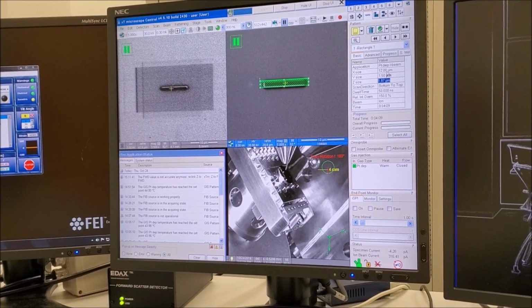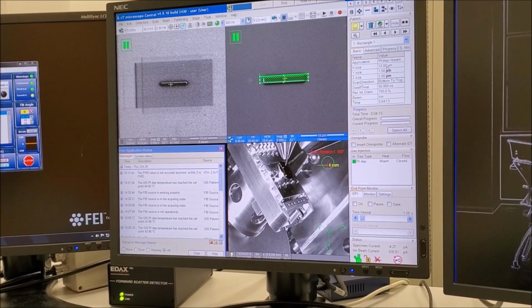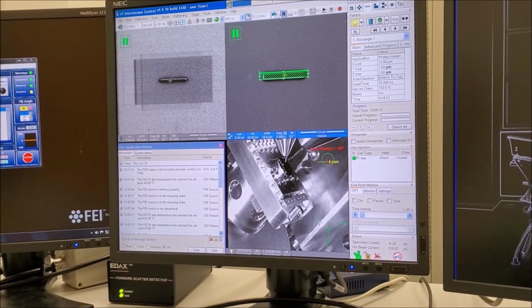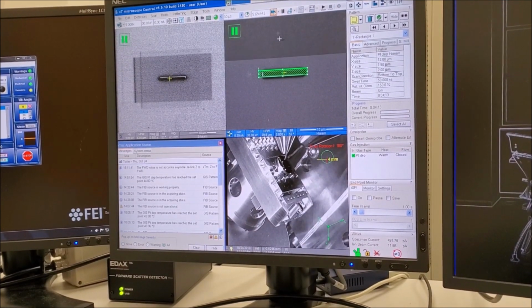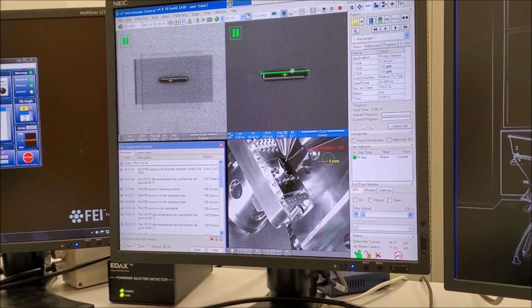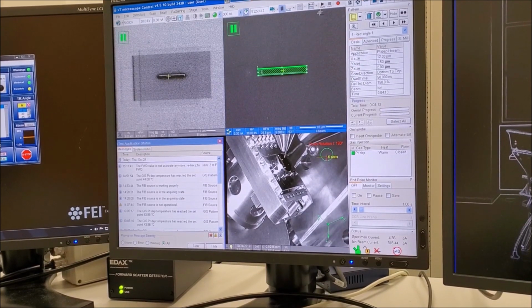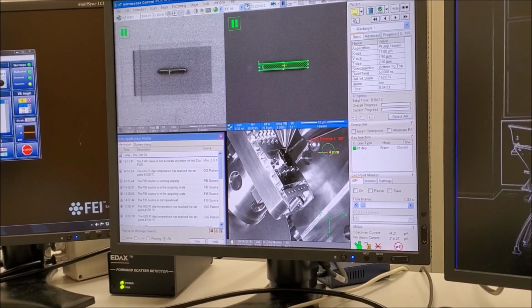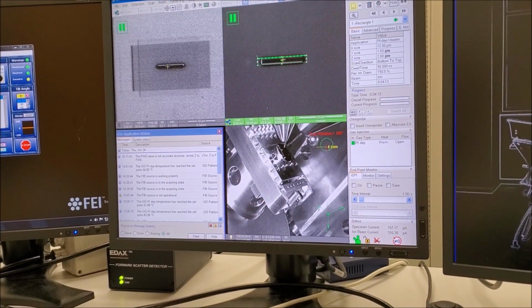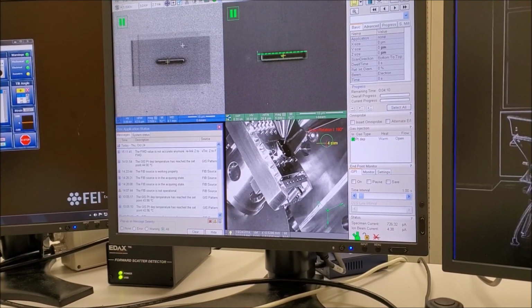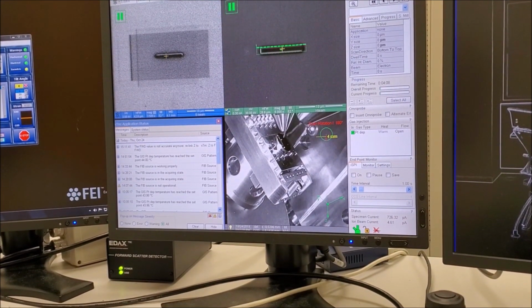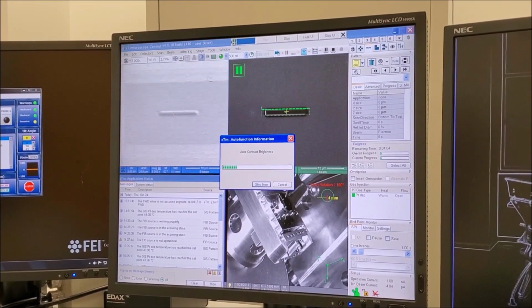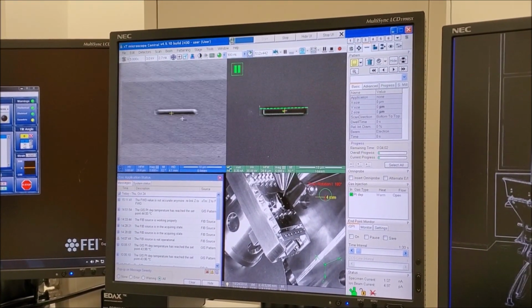Keep in mind that for PT deposition to be effective with the ion beam, the current density should not exceed a few tens of picoamps per micron squared. Take one final I-beam snapshot and then position the pattern as needed. Then select the play button to start deposition. The progress of the ion beam platinum deposition can be viewed in real time using the electron beam. Activate the electron beam quad and then unpause it.